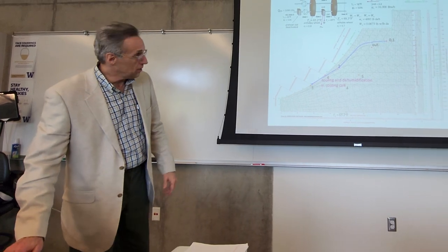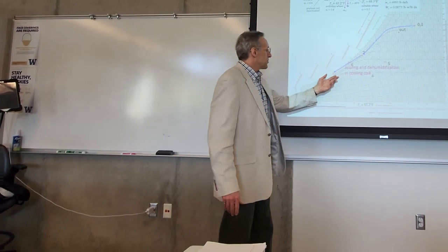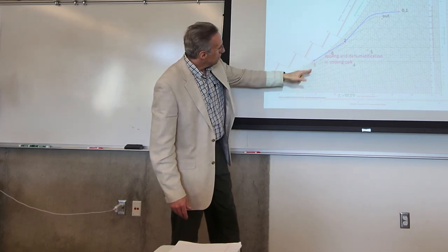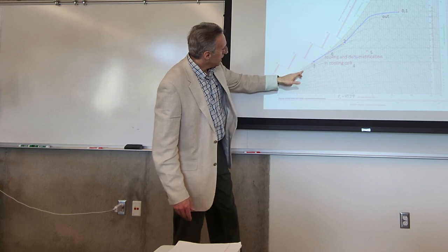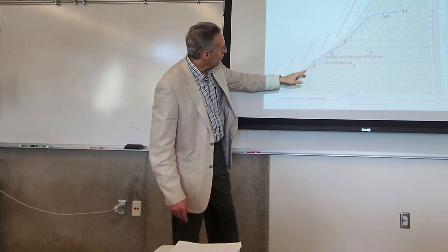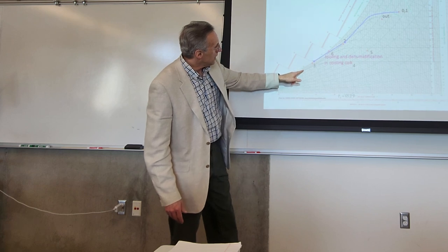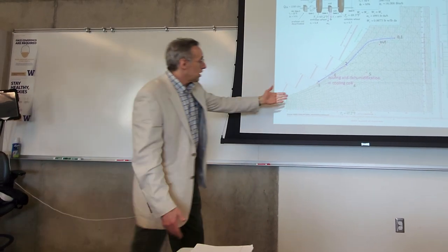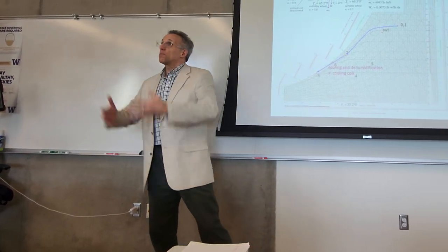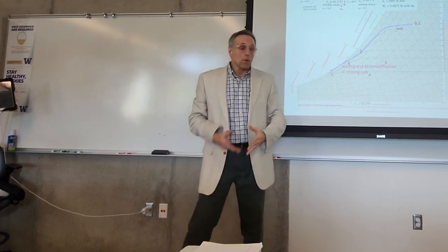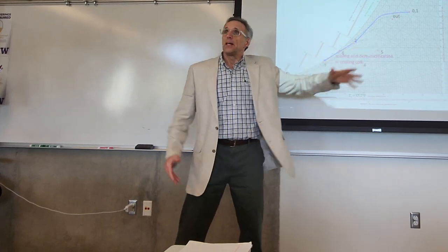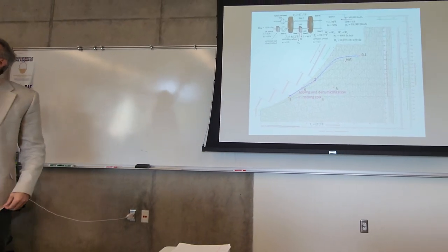But too cold to put into the... In most cases, we wouldn't be quite that cold. Well, actually, we would. Because this is actually a little bit warm for a DOAS. Often we're down here. The nature of the system is that often we just take this air and mix it with return air in the plenum and then put the mixture into the space. But we can also just put this directly into the space and allow it to be entrained with the room air and to mix with the air that's coming from the chilled beam or from some other place.